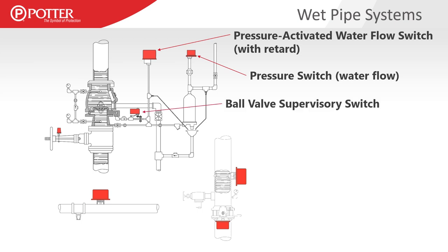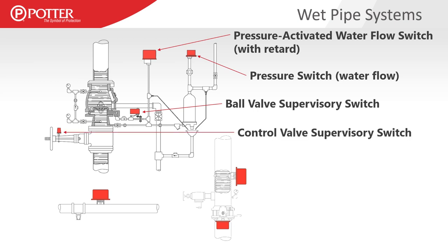Anytime you have a valve that controls flow or pressure to these pressure switches, we have to have a supervisory switch or that valve has to be supervised. NFPA 72 requires that in order to prevent us from inadvertently leaving that valve shut and rendering that pressure switch inoperable. Valve supervisory switches come in different types and styles, each with their own inspection, testing, and maintenance requirements.